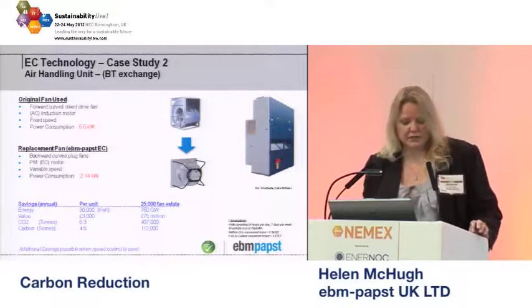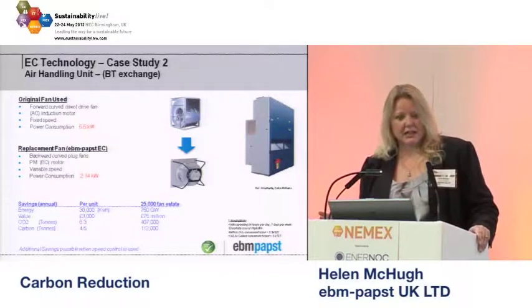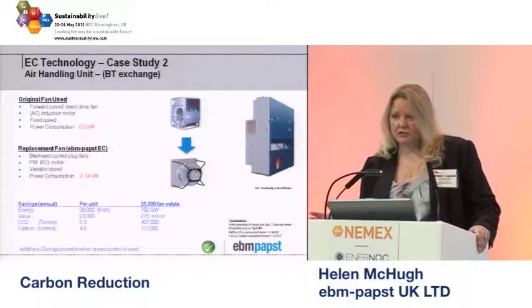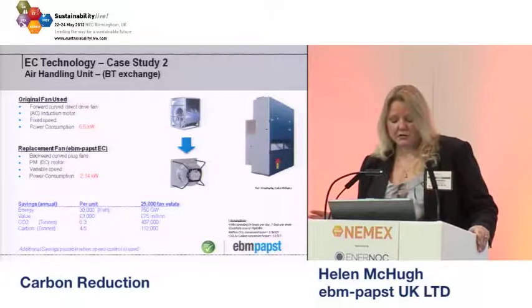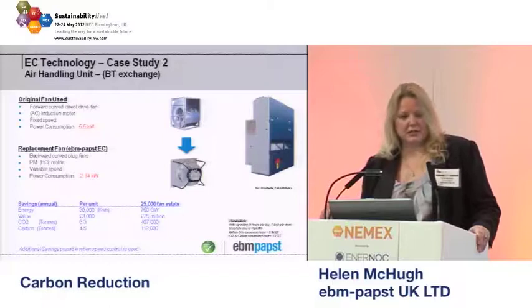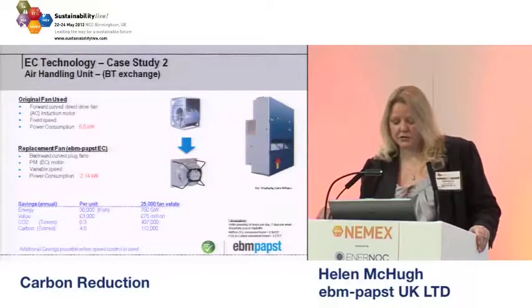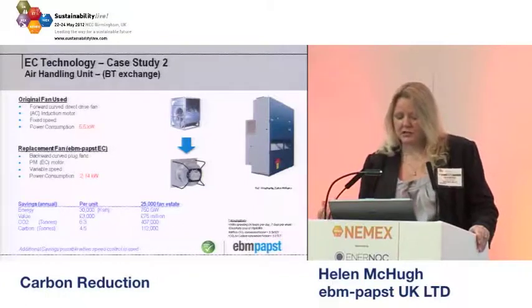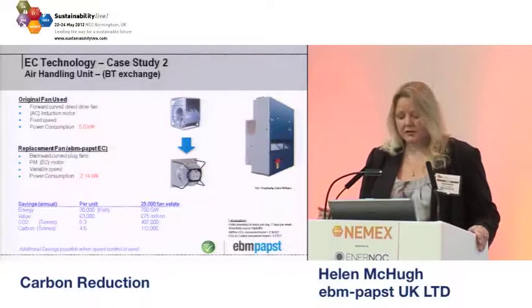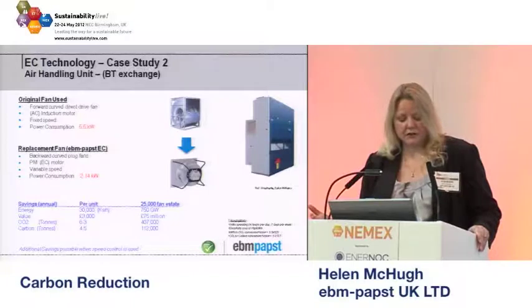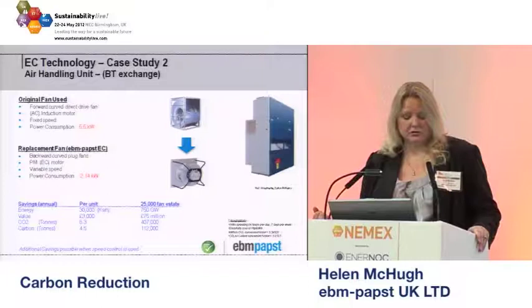Another example here is for an air handling unit. In this case, it was for BT, and we're looking at swapping out a traditional forward curve blower and swapping that for our high efficiency motor in a different design of fan as well, so a backward curved fan. And again, we're looking at an initial power consumption. This is operating at a fixed speed of 5.5 kilowatts. By simply swapping to the new fan, we've halved that, so we're down to 2.1 kilowatts.